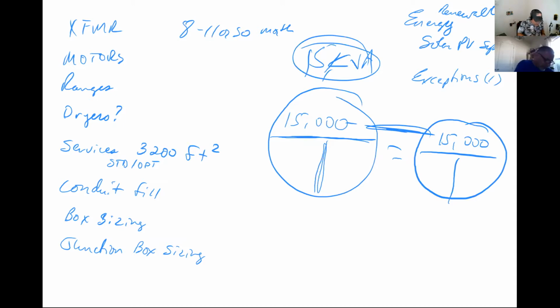All right, now we did all that math, right? And the whole purpose of that was to just understand the rough calculations for it. But if I'm using this table to size a breaker, that 125% has to be applied to some number. And so what we were doing was trying to figure out on that primary side, what is that FLA for that transformer? What's the full load amperage of that transformer when it gets up to full load there? What are we looking at?